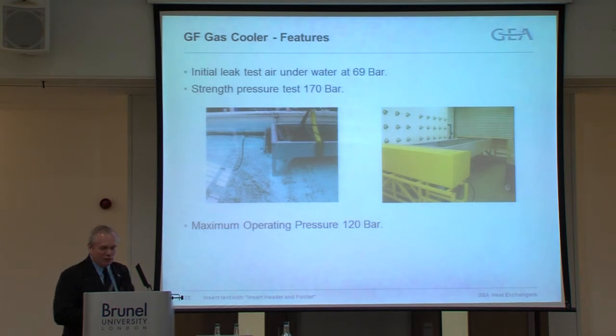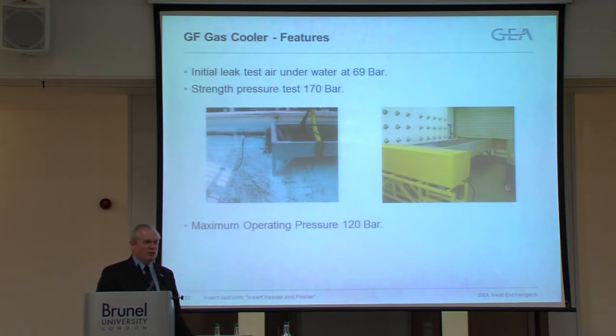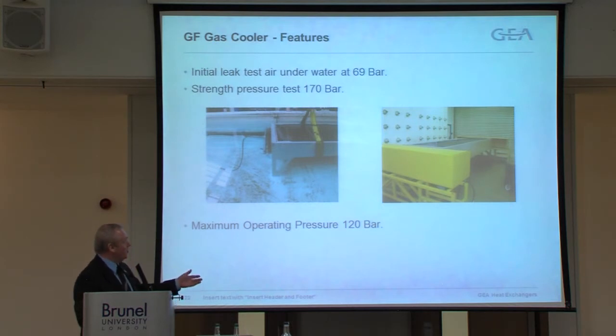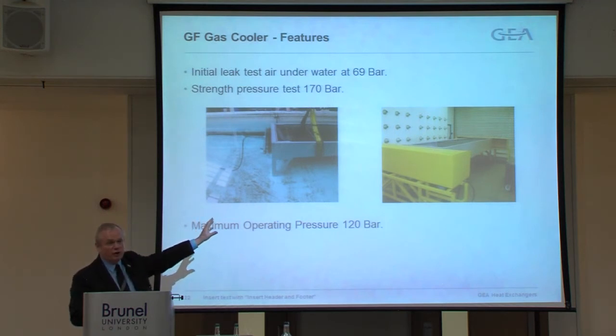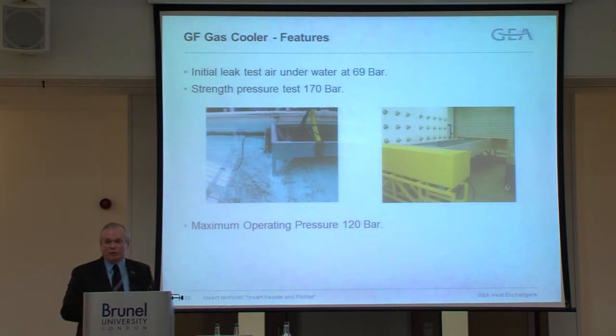Testing created a little bit of a problem for us. When you're testing at 30, 40 bar, you stick it in a tank, put it underwater, pressurise it, see if you get any bubbles coming off it. Obviously, with the CO2, we've got operating pressures of 120 bar. So we're doing a leak test, underwater, using air with a dew point of minus 30 degrees C, and we pressure test it to 69 bar, looking for any leaks. No leaks, then we put it in a special tank at Searle. We put these yellow header caps over the return bends and the headers, and then we pressurise it up to 170 bar.